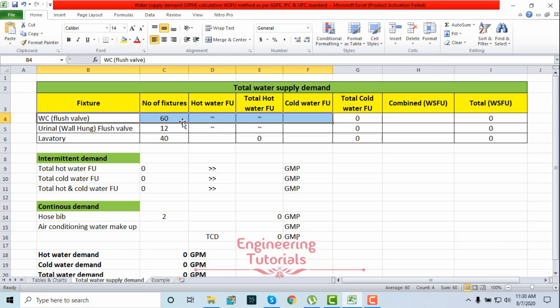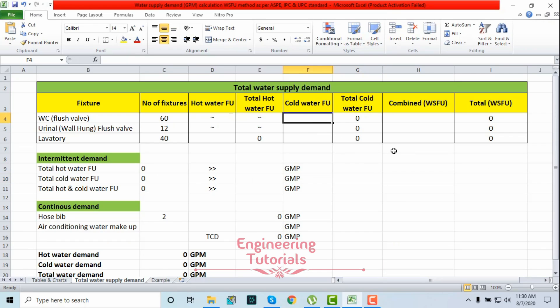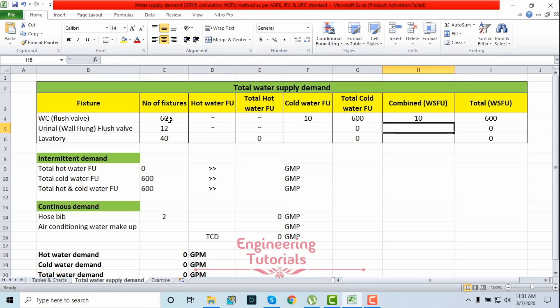The first fixture is the water closet and the number of fixtures is 60. There is no hot water required for this one, so we look at cold water fixture units and total water fixture units. Since this is an office building we select public occupancy, and the supply type is flush valve. For a water closet, public, flush valve: cold water fixture units are 10 and total water supply fixture units are also 10. So in our Excel sheet, cold water fixture units = 10 and combined = 10. For 60 fixtures: 60 × 10 = 600 total water supply fixture units.